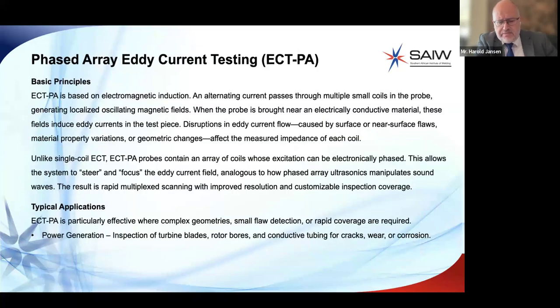Phased array eddy current is based on electromagnetic induction, and alternating current passes through multiple coils in the probe, generating localized oscillating magnetic fields. When the probe is brought near an electrically conductive material, these fields induce eddy currents in the test piece. Disruptions in eddy current flow caused by surface or near-surface flaws, material property variations, or geometric changes affect the measured impedance of that coil.